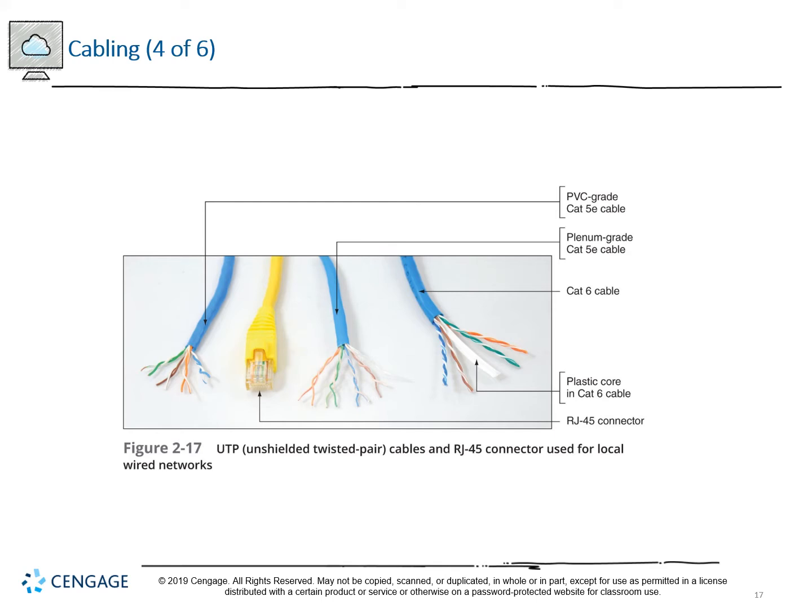PVC, or polyvinyl chloride, is a type of plastic that when burned emits a toxic smoke. Toxic smoke is very much something you want to avoid if you are a remotely carbon-based life form. So we instead use what's called plenum graded cable, because plenum is the space between the ceiling of one room and the floor of the next in a multi-story building, or if you're just talking about the space between the ceiling and the roof or an attic. In the event of a fire, when that burns, it will not generate toxic smoke, and it's also a little bit more fire resistant for the majority. Now, because it is a specialized material, it is more expensive to make. So plenum rated cable should be specifically run for things that require it, not for every entry.